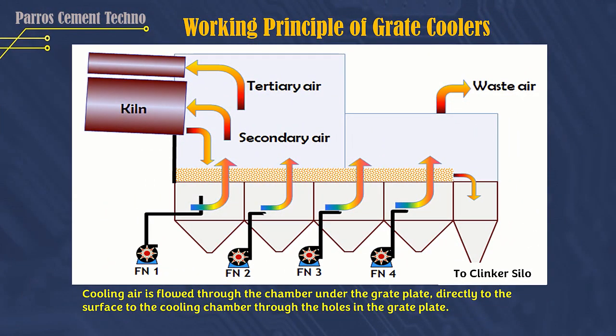Working Principle of Grate Coolers. Cooling air is flowed through the chamber under the grate plate, directly to the surface of the cooling chamber through the holes in the grate plate. The clinker material that comes out of the rotary kiln falls on the grate plate and moves out of the grate cooler, due to the thrust of the grate plate which moves forward and backward continuously.